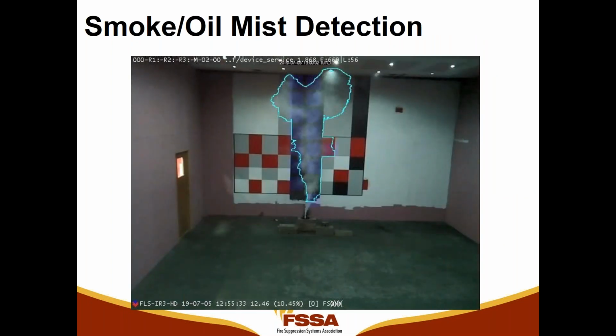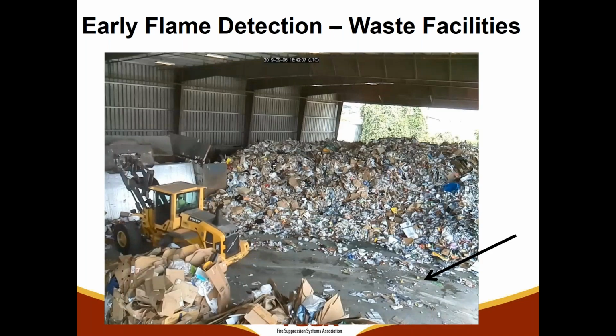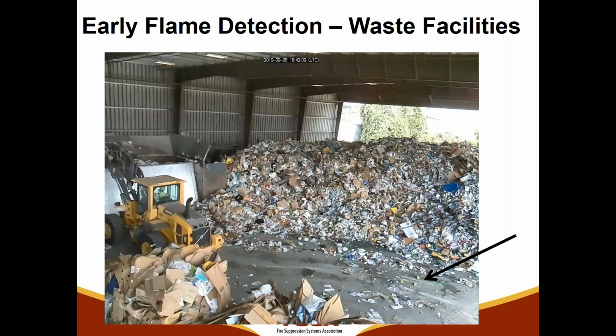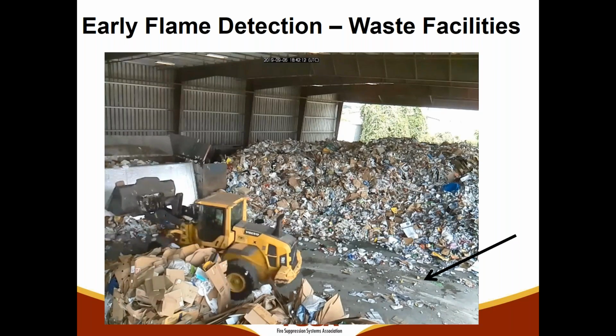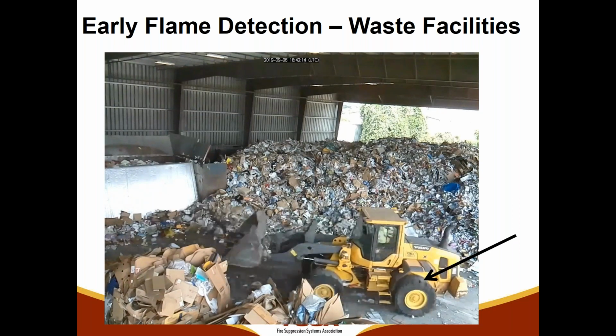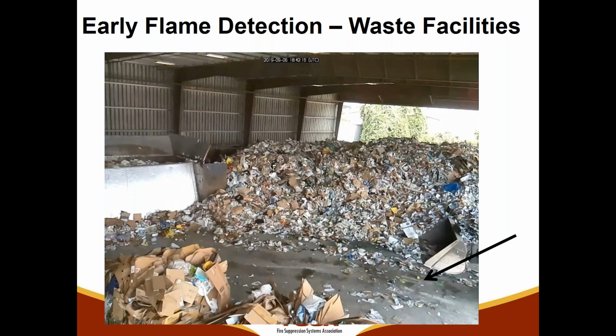Okay. So this is a video of the analytics monitoring for smoke through the triple IR camera. Very good image. This is an event that we caught at a waste facility. We installed the camera on a Thursday. We went back the next Friday to view the events on the detector itself. There was one event, and that was a fire that occurred the day after we installed the detector.